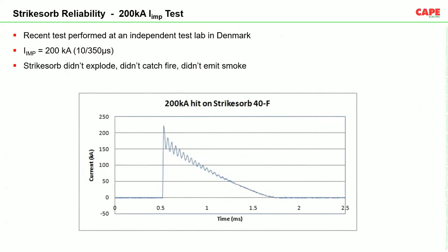Apart from that, we have tested Strikesorb 80 model and Strikesorb 40 model with a single impulse of 200 kiloamperes 10/350, which is the highest possible positive impulse current, 200 kiloamperes in Level 1. We have seen in LPL1, the maximum expected 10/350 current was 200 kA. So we have tested Strikesorb 40, even though in the earlier parameters we have shown 12.5 kA only, but still additionally we have tested Strikesorb 40 with 200 kA 10/350 impulse current. And the result was Strikesorb didn't explode, didn't catch fire, and didn't emit any smoke. This is a chart of the testing.